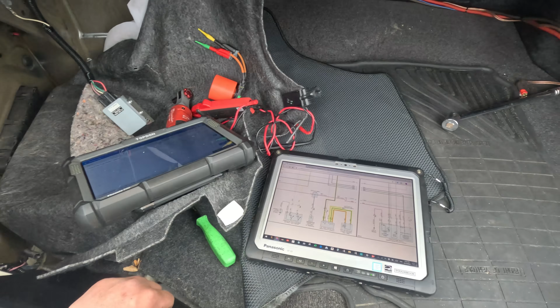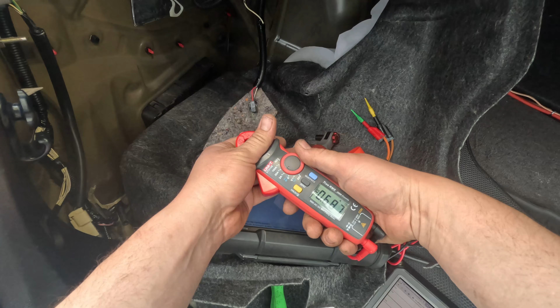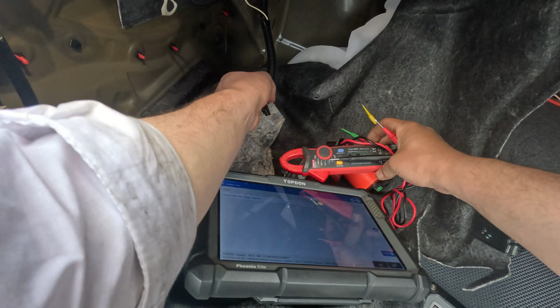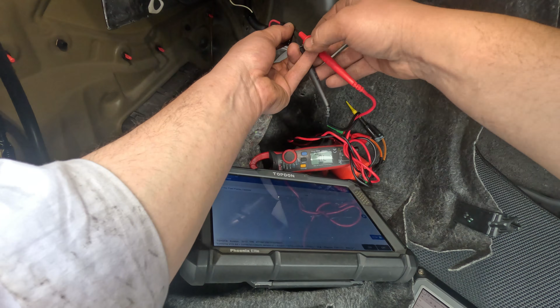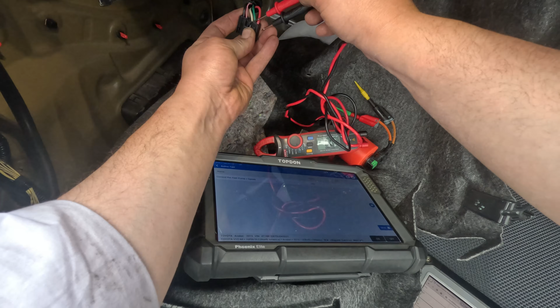Now, do we have continuity through the pump? That's what I want to see. So let's just check right here. We'll pop this out. Let's set this to ohms. Now we should have some sort of continuity through this pump. Probably like 2 ohms. Red and green, and we got nothing. We have an open circuit. We have absolutely nothing through this pump. Let me try to back probe it just to make sure it's not in the connector. Make sure my meter's working. It is.